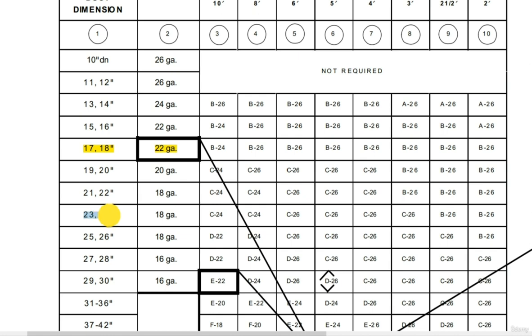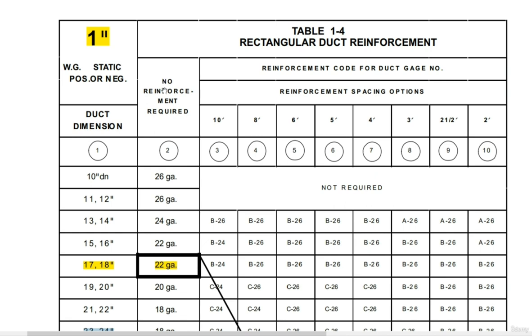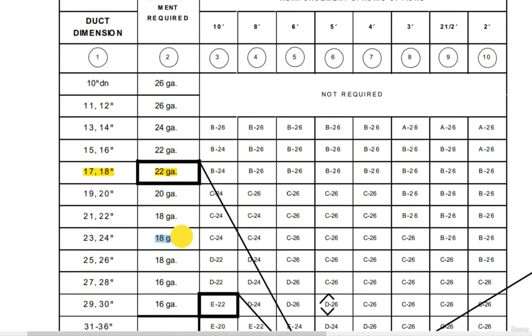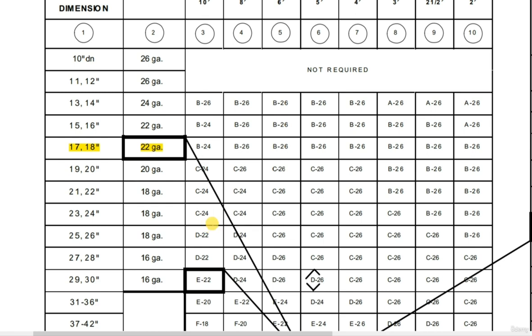For example, with a 24-inch duct at one-inch static pressure classification, no non-reinforcement option is given at gauge 18. However, if the duct gauge found on site is gauge 24, you can use the reinforcement option. This gives you reinforcement type C, or minimum rigidity class C, with a sheet metal thickness of gauge 24. Problem solved — without mistakes, material returns, or unnecessary embarrassment. I hope this example has clarified everything. Let's now go back to the presentation to work through a small example.